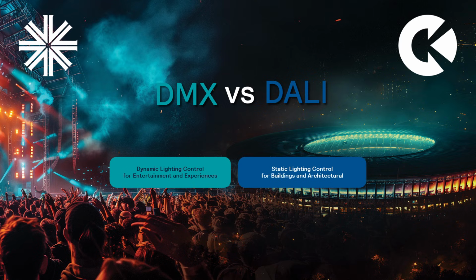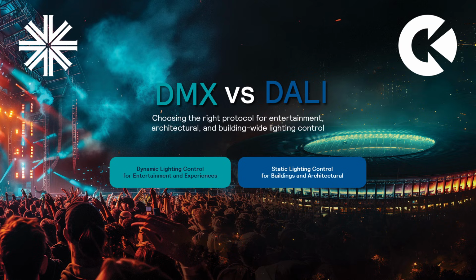DALI is intended for white light installations where fixtures are generally creating the same effect, such as intensity, at any given instant. That distinction is the foundation for everything covered in this presentation. It explains the differences in architecture, performance, scalability, and application suitability. As you'll see throughout the module, both technologies play important roles in modern lighting systems. The key is understanding where each protocol delivers the greatest value.